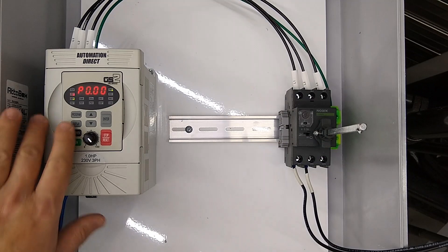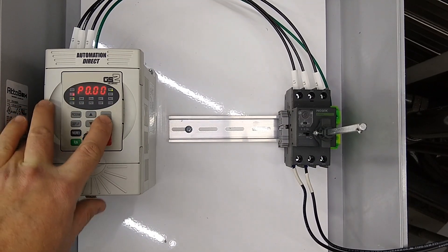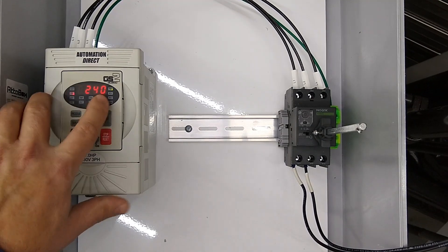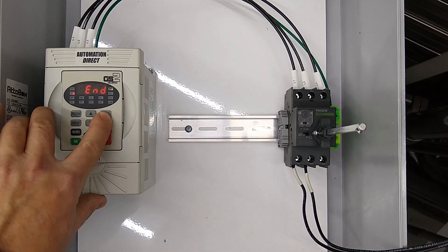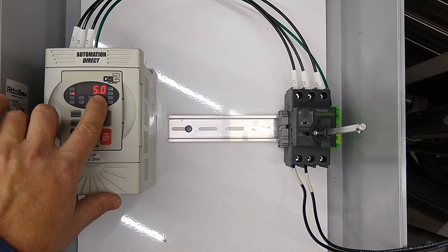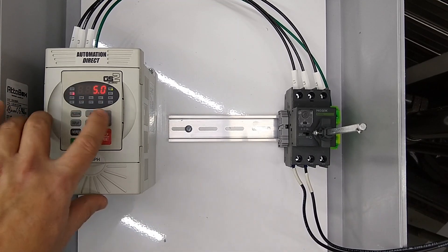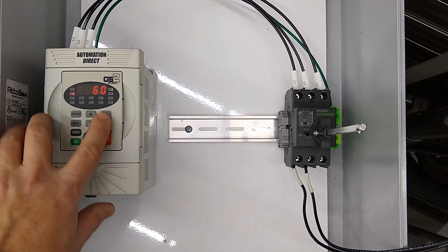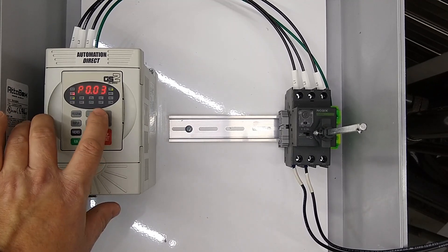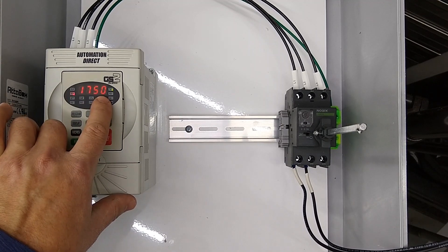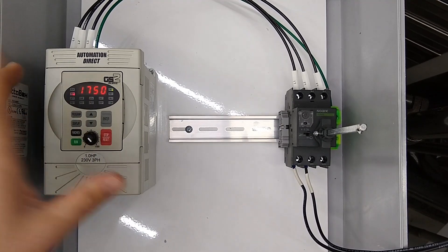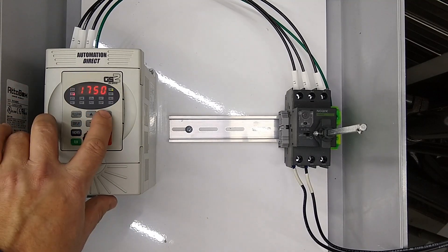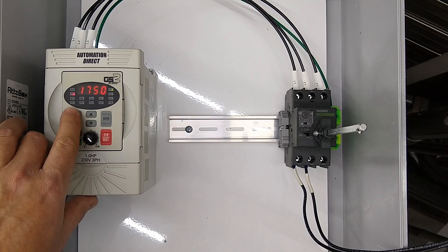A few other parameters that you need to be aware of and probably just verify that yours is close to: you have your nameplate voltage, which in our case is 240 volts, and then we have our nameplate amps, which is five. You want to adjust this to what's on the nameplate of your motor. Then we are base 60 hertz and our base RPM is 1750. You want to check your nameplate—make sure it doesn't say 1800 or 3600 or something like that.